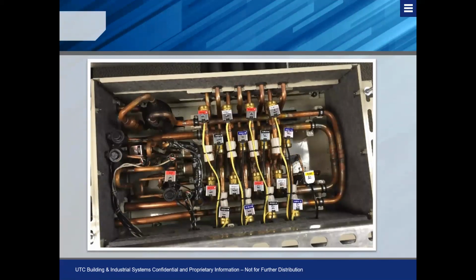So if we take a look inside one of these selector boxes, one of the biggest advantages with the Carrier 2-pipe systems is that these service boxes, as far as solenoid valves go and actually being able to work on the box, are fully serviceable. This is something that our competitors cannot claim because the inside of their box is insulated, and that is to prevent the box from having a drain on it. Well, from my service background and the way that I look at things, I would much rather sacrifice having a drain and trying to figure out where to drain so that I can work on this box and replace individual solenoid valves, instead of having to leave an extra port on a box to unpipe a unit from a port that, let's say, has a failed solenoid over to another port that's working. So that's one of our biggest advantages with the Carrier 2-pipe system: a fully serviceable flow selector box.